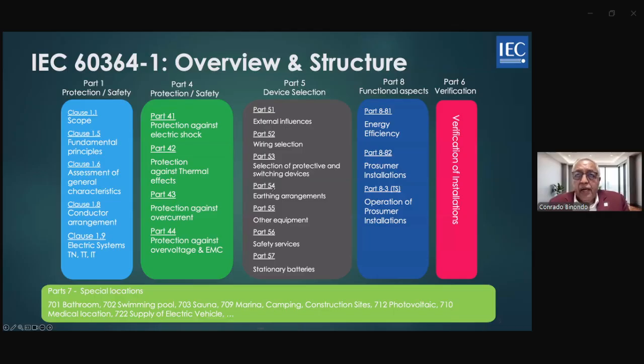Then in part 54, we have the earthing arrangements. In part 1, you have the electric systems like TN, TT, IT, but those are for the source. When you enter the premises or installation, you have to properly arrange your grounding and bonding—what the code calls equipment grounding conductors, bonding of all exposed conductive parts, and also the grounding rods, how they're implemented, their size, and so on. All of this is included in the earthing arrangement.